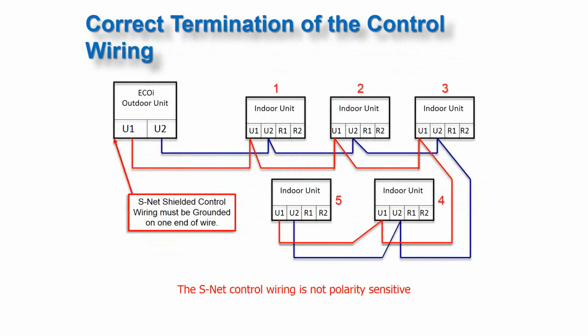Okay, so this is an example of a correct wiring setup for an ECOi unit. We have U1, U2 at the condenser, and you have U1, U2 at all of your indoor units. So this is a good snapshot of what the communication link is going to look like. You're going to go from your condenser to your first indoor unit, second, third, fourth, fifth. We always want to use 18 gauge 2 conductor shielded wire.